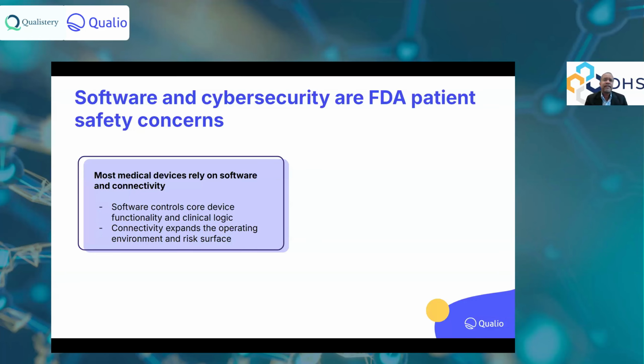So I'm going to talk about software, right? Software and cybersecurity are super important, for obvious reasons, to FDA for safety concerns about the patient, right? A software failure may stop your heart pump, right? Cannot happen. Somebody would die. The software is absolutely part of that. When you do software risk analysis, you write code for software, that's your own code, and you need to comply with 62304, including risk analysis identified by that standard, of course, besides 14971 and doing all design controls.